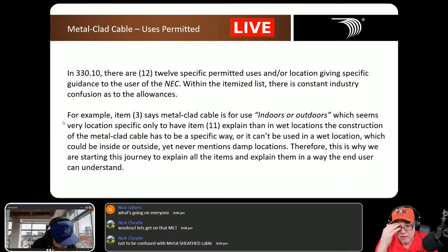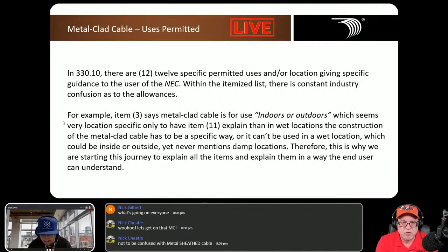But MC is a dry location product, so to use it in a wet location, certain things have to be done, which we'll look at when we get there. This causes confusion because people see item number 3 saying MC can be used outside, only to later learn that for a wet location it must meet a certain construction design to be used.